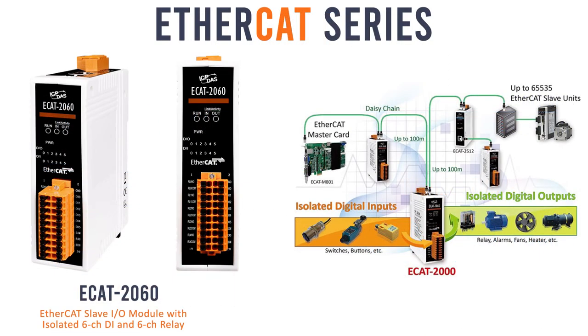EtherCAT is the fastest industrial Ethernet technology and synchronizes with nanosecond accuracy. The EtherCAT master is the only node allowed to actively send an EtherCAT frame. All other slave nodes merely forward the data on the fly or fill data into the frame as it is moving. This concept guarantees real-time capabilities, and the frame is delayed only by hardware propagation delay times. The rapid reaction times reduce wait times during transitions between process steps, so EtherCAT's excellent performance leads to improved accuracy and great throughput.